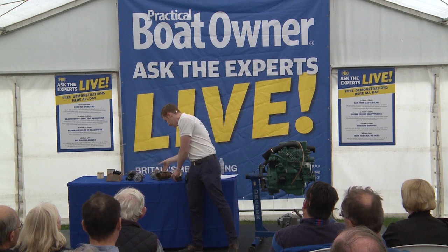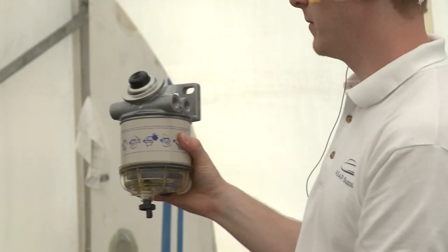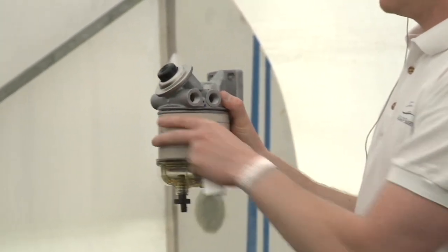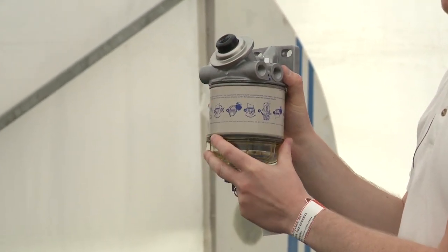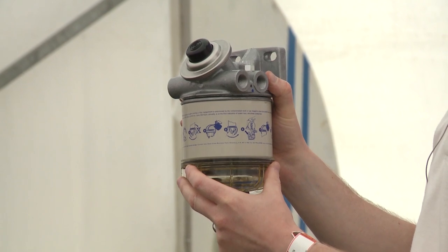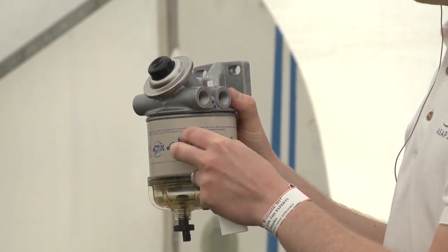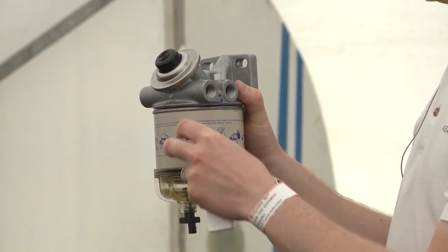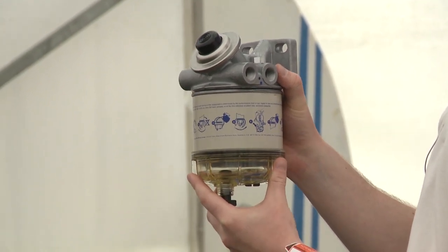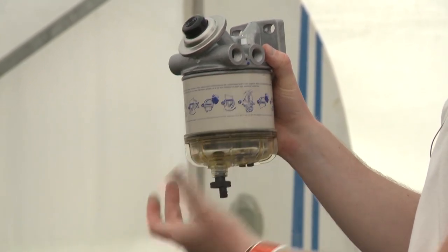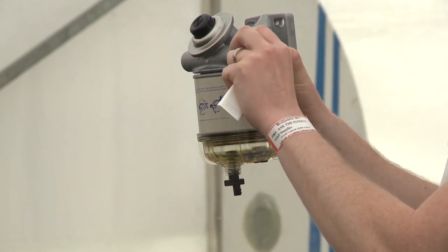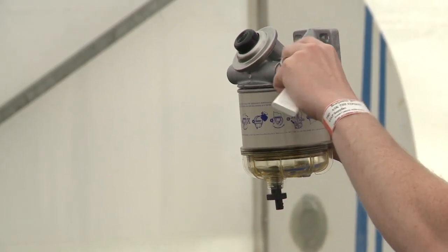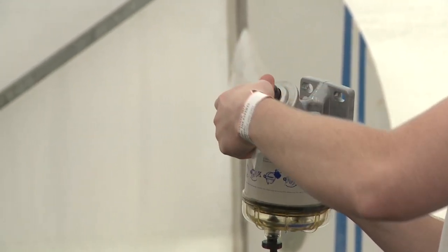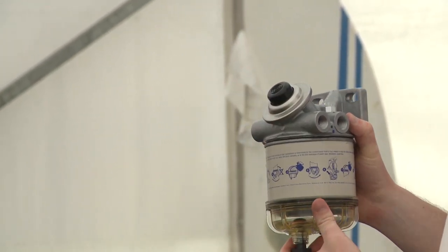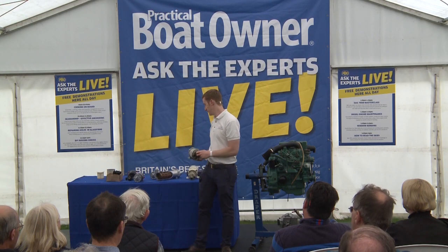With this one, when it comes to servicing, you undo this bowl and the element and the bowl come off. You then throw away the element, put the new element on the existing bowl, fill this up with diesel, and then screw it back on. The only air you should really get is what's in the top there, and if any comes out the fuel line. Then obviously this is where you pump it up and that'll force the air back out of the system. So it's quite a bit easier.